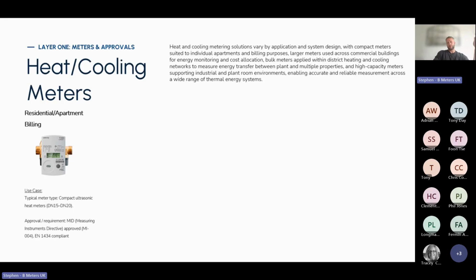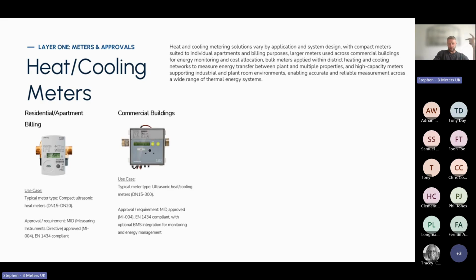That doesn't really change. So whereas water has a little bit more variation on, okay, we may need a higher classification, all heat meter manufacturers tend to try and meet the same standard, which is MID class 2. So all ultrasonic, Kamstrup, Diehl, Itron, Landis, they all tend to be MID class 2, EN 1434 compliant. So as you go through it, it's the different types. So, for example, you've got a Landis UH50 for commercial buildings, which just has a much more varied range. So you can get DN15 up to DN300 up to, if required, 500, 600.